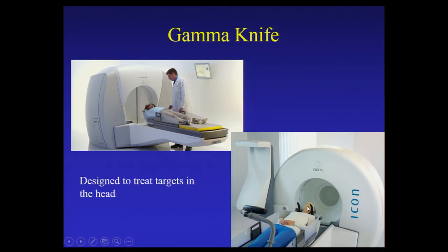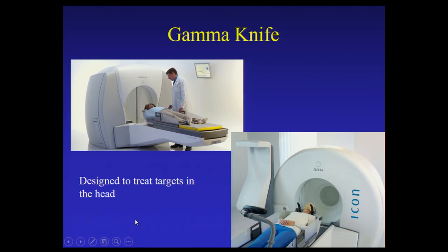Down here is the latest version of the gamma knife unit, which we will presumably receive early next year. It's slightly different — it does not involve a frame bolted to the head. It's a frameless system using a mask, and it has an onboard CT scanner that helps us localize the tumor in near real time.